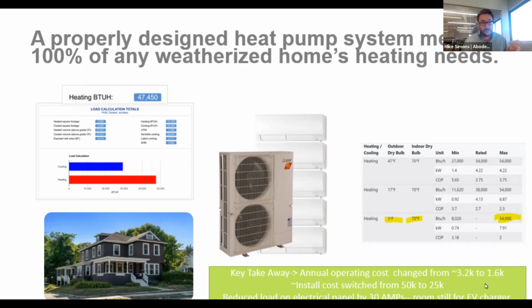The last thing that I think is really important: if you're putting in, say, two large outdoor units because you still have a massive heat load, each of those outdoor units is going to take up real space in your main electrical panel. We have a lot of things to decarbonize and electrify, and if you're chewing up all the capacity in your main panel with air source heat pumps, you're not leaving space for decarbonizing your transportation, your domestic hot water, or putting in an induction cooktop. That's another thing I think is important to keep in mind.